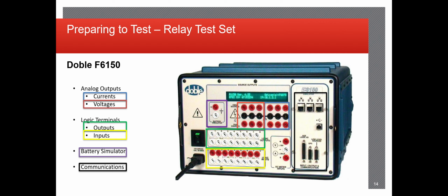So you see in this blue section right here, and the red section as well, those are your current and voltage outputs. Those you'll connect to the current and voltage test switches or back of the relay terminal blocks if need be. The nice thing about those as well is that you can change them in the software. So you could actually flop them, have the currents be on the left and the voltages on the right, or even just have all voltages or all currents if you're doing like a differential test or something like that.